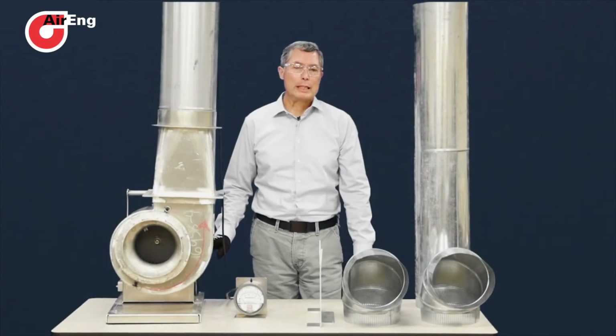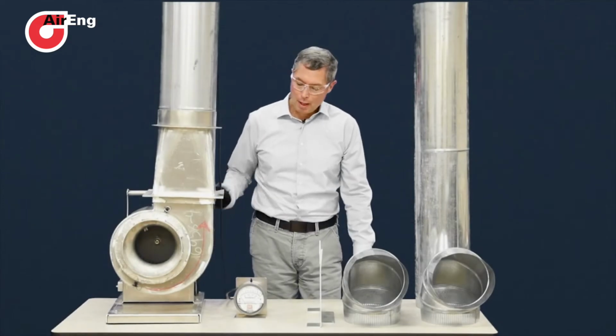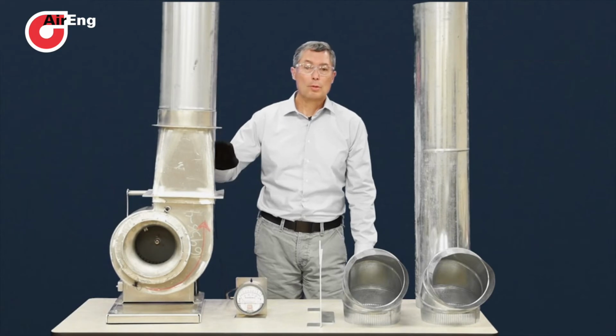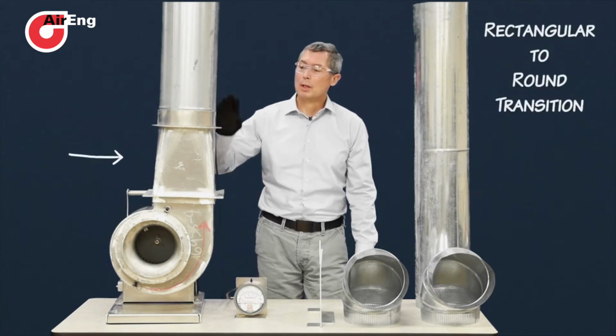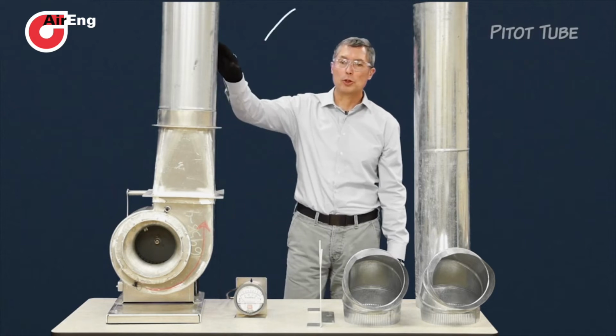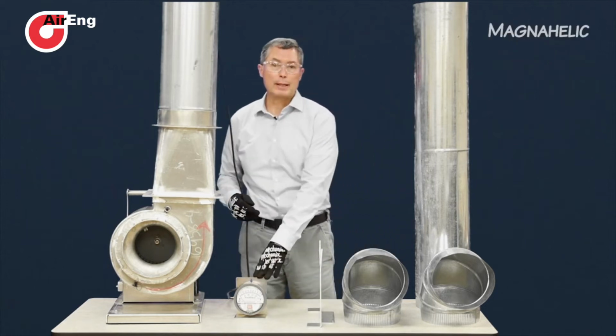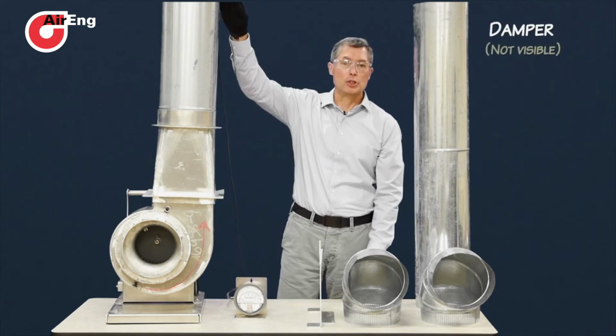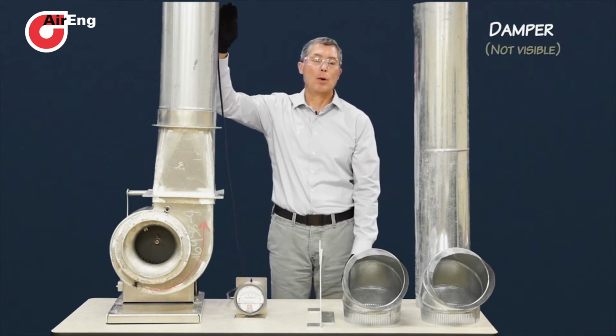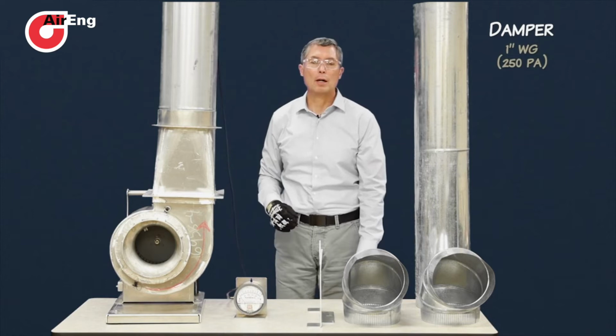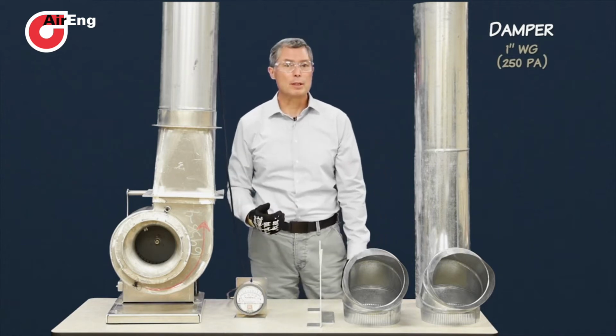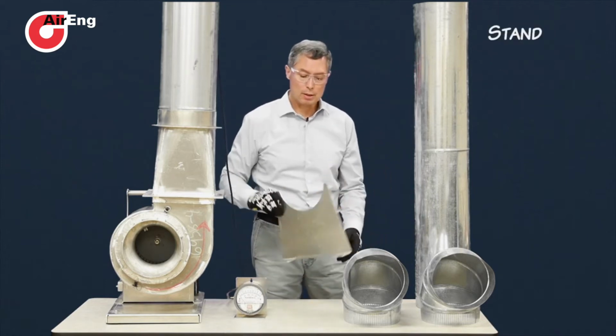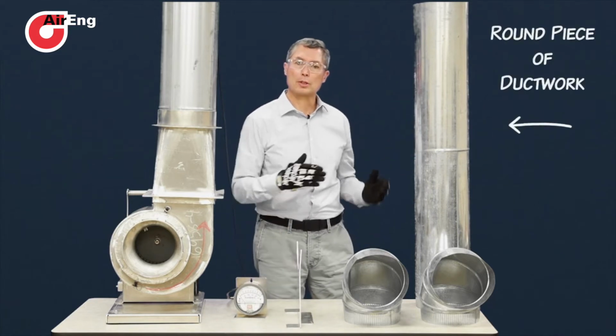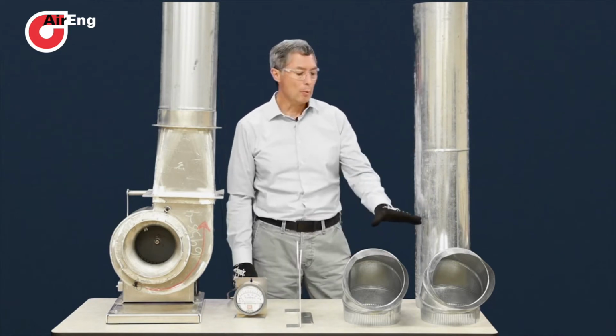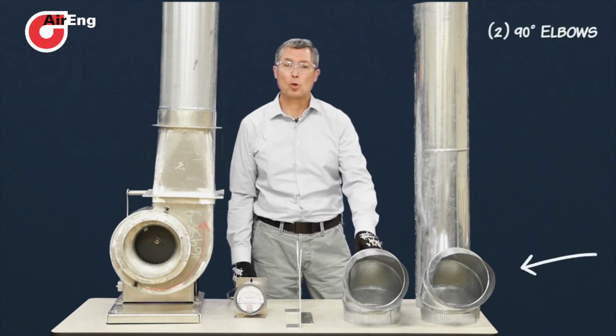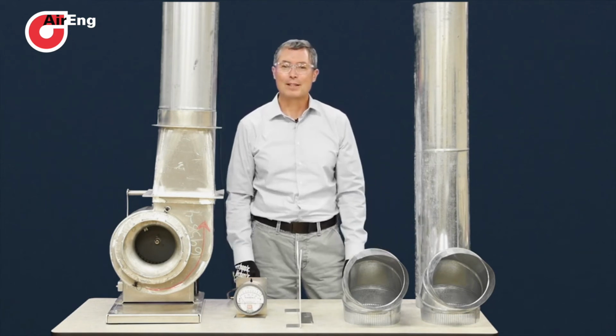Let's talk a little bit about the equipment required for the demonstration. We have a fan blowing into a rectangular to round transition, a round piece of ductwork that includes a pitot tube, some tubing that goes to this magnehelic gauge. We have a damper at the discharge, and that damper is preset at about 1 inch of water gauge or 250 Pascal, and that's going to be our baseline resistance setting. We have a nice little stand here to support this round piece of ductwork so it doesn't topple over while we're doing our demo, and we have two 90-degree elbows to create our corkscrew. Thanks, and on to the demonstration.